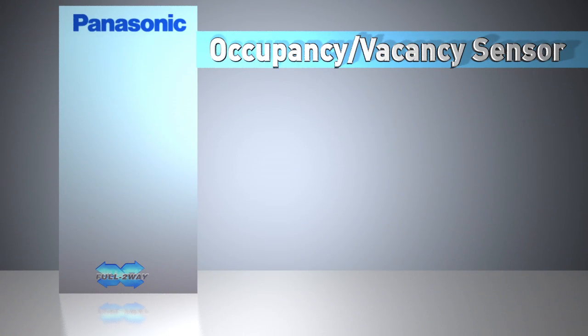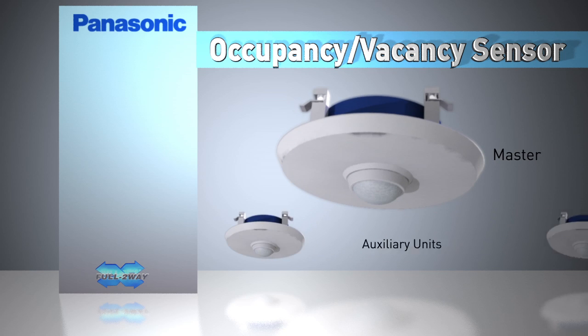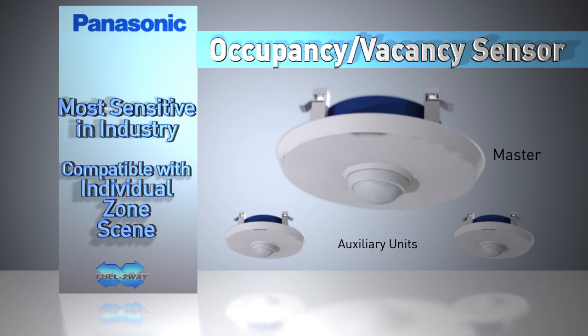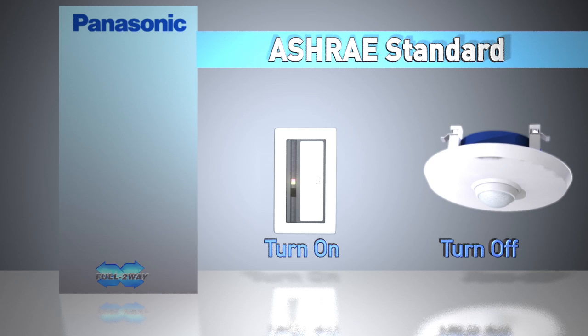Full two-way also provides occupancy and vacancy sensing. An occupancy sensor detects movement in a range area. In fact, the Panasonic minor motion occupancy sensor can detect the slightest movement, reducing or eliminating a false off while the space is occupied. Occupancy sensors can also be addressed for individual, zone, or scene lighting. One energy-efficient control method and also an ASHRAE standard is using a manual switch for on and a vacancy sensor for off.